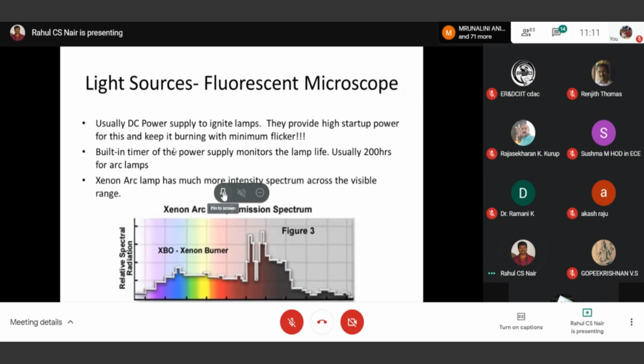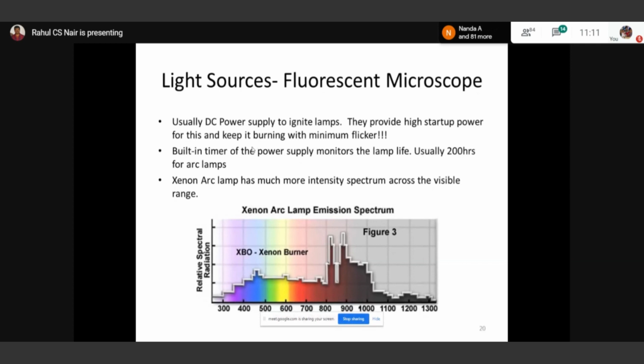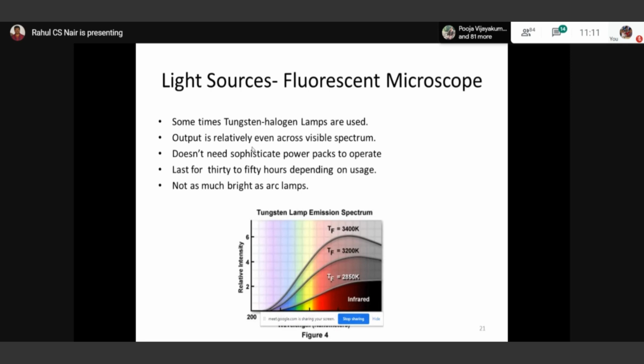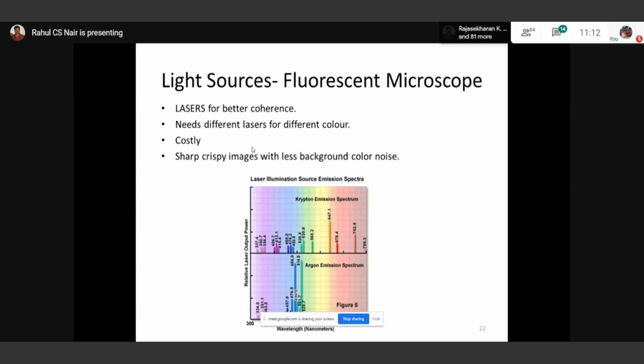So this is a spectrum of xenon arc lamp. As compared to the earlier one, the mercury arc lamp, it provides a much better spectrum of light, especially in the visible region. These are the two common light sources that we are using. Apart from this, tungsten sources are sometimes also used, and tungsten is also a very good light source. Now, the most advanced microscopic techniques use lasers, because lasers are very crisp and highly coherent. You need to use different lasers for different spectra, because that is the only disadvantage. You need to use a green laser, red laser, like that. Also it is costly compared with the other light sources, and you see the sharp emission spectra from lasers.